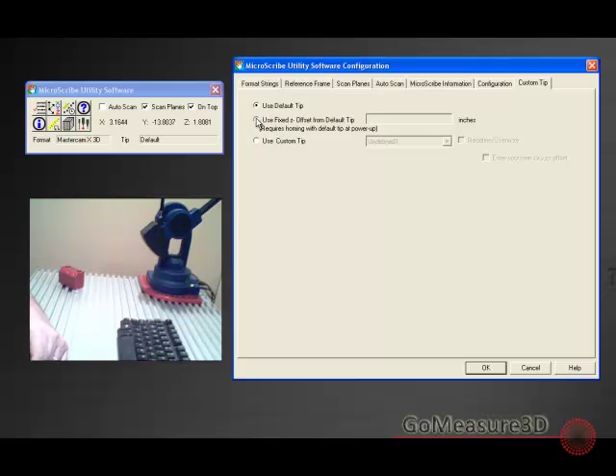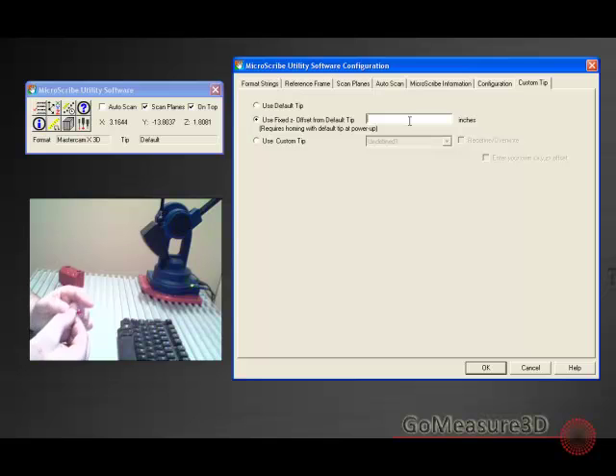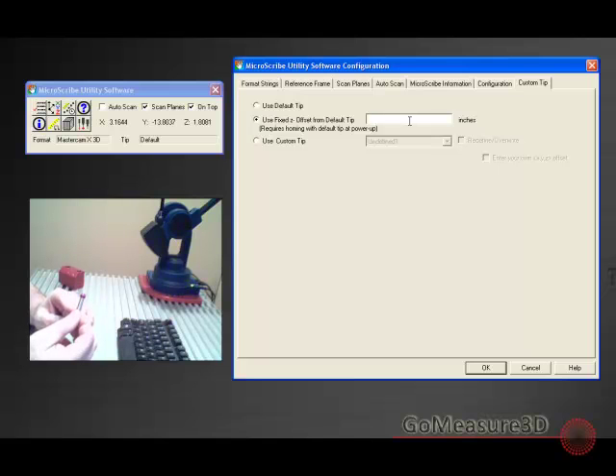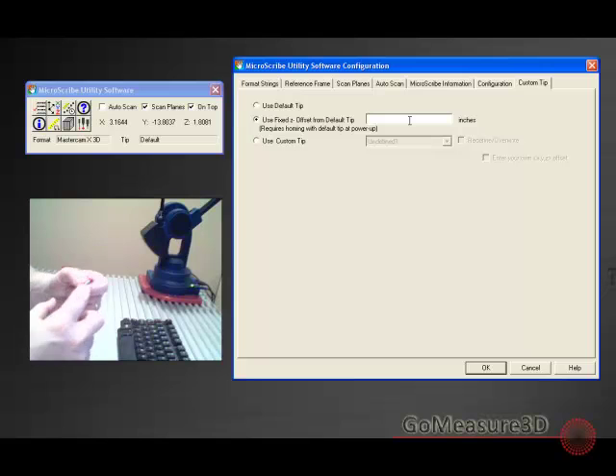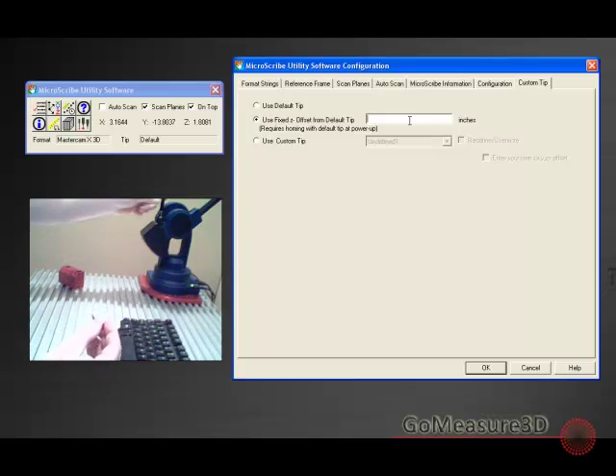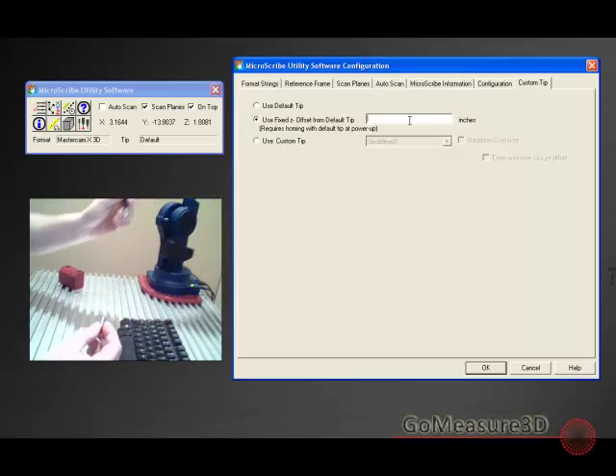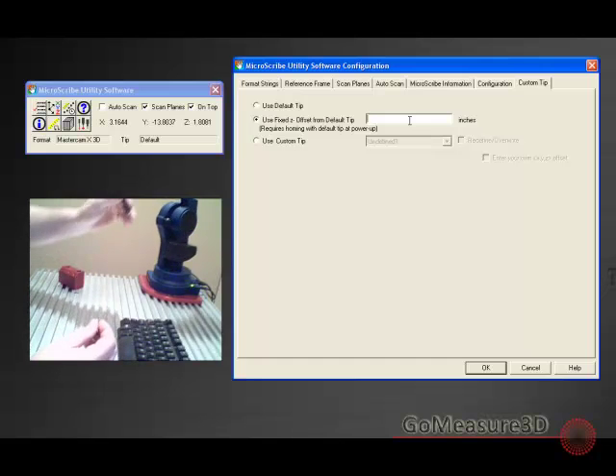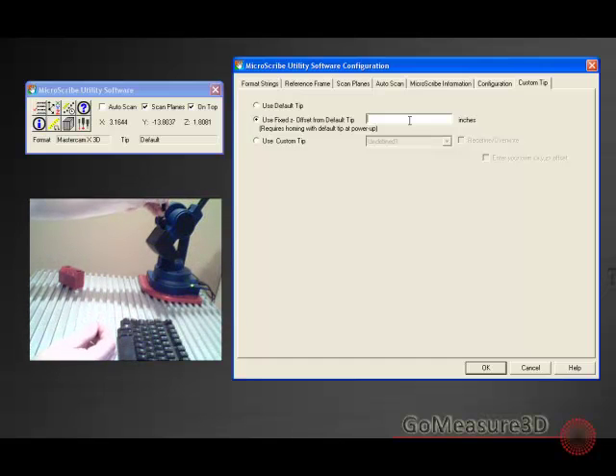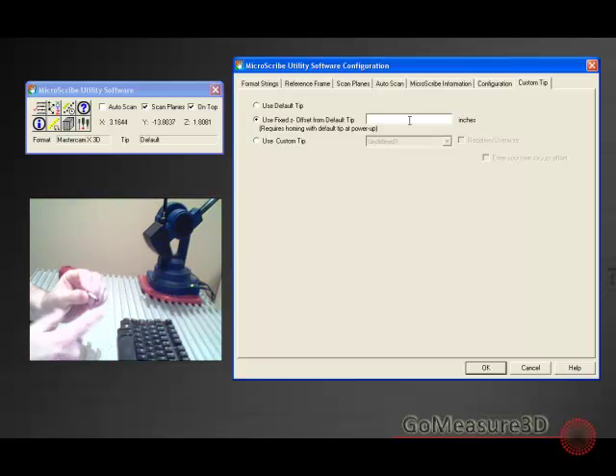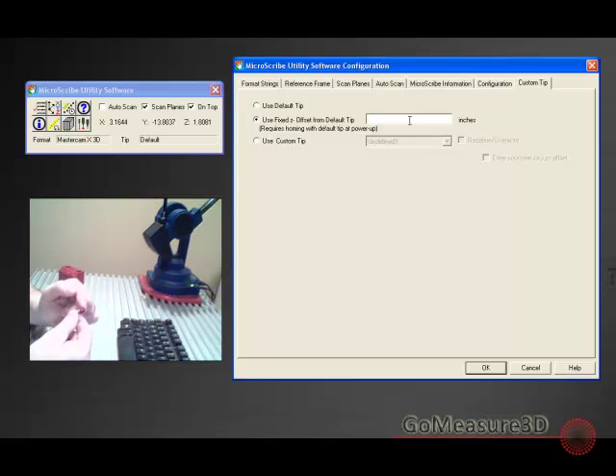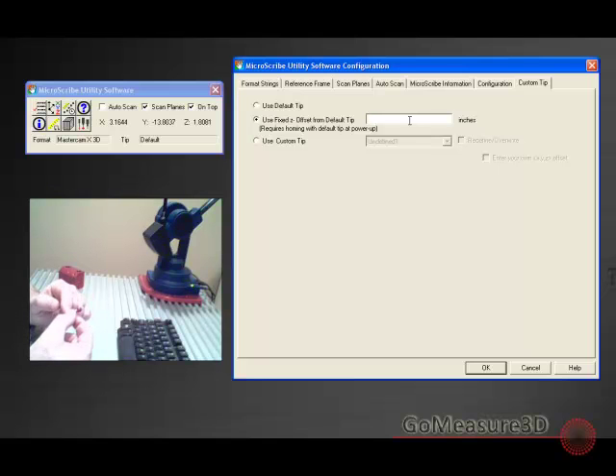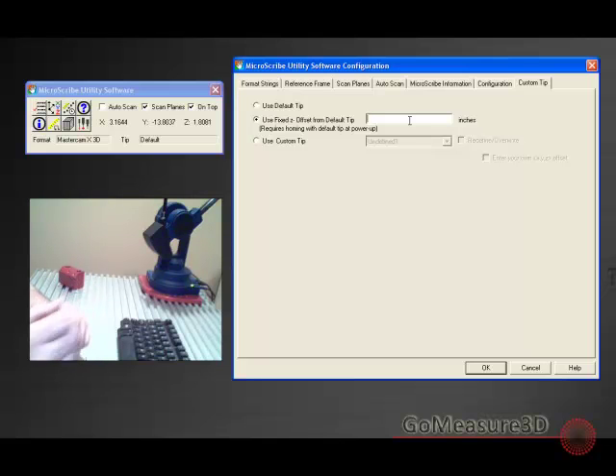We could check this radio button and then put this information in. Now, keep in mind, offsets are inverse or the opposite of the measurement. So if we were to put a one inch extension on this probe or extend this probe out one inch, we would put in an offset of negative one. Or if we were to put in a probe that had a smaller offset, we could just put in a positive direction. So smaller is positive, larger is negative.